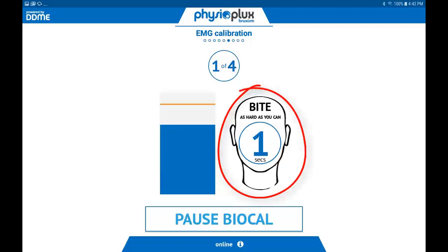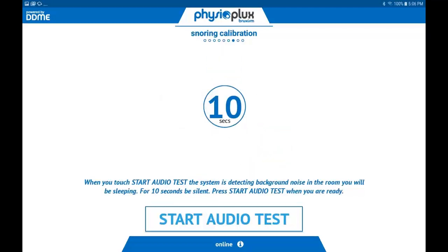These instructions will repeat 3 more times, and once 4 bites are collected, the tablet will automatically advance to the next page. It is important that you bite down as hard as you can. Do not worry if the bites and relaxes do not occur exactly when instructed. It is more important to record 4 hard bites through this calibration. If the system does not detect the bites, you will be prompted to repeat the BioCal. Once the BioCal completes, the screen automatically advances to the audio calibration page.